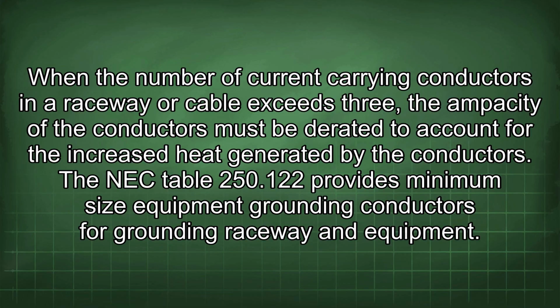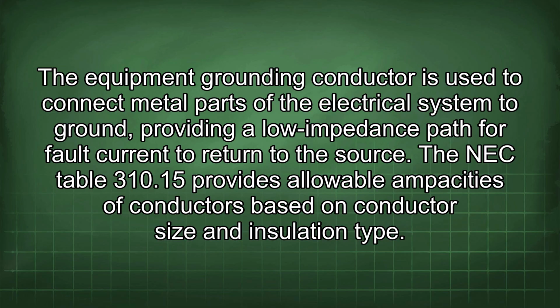The NEC Table 250.122 provides minimum size equipment grounding conductors for grounding raceway and equipment. The equipment grounding conductor is used to connect metal parts of the electrical system to ground, providing a low impedance path for fault current to return to the source.